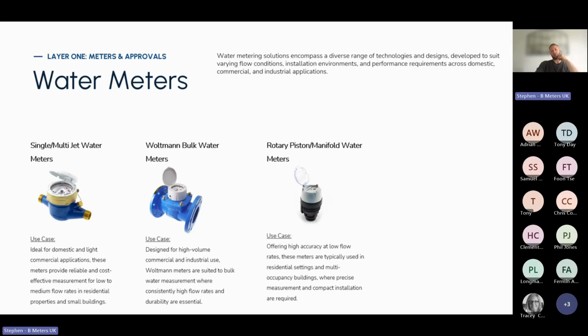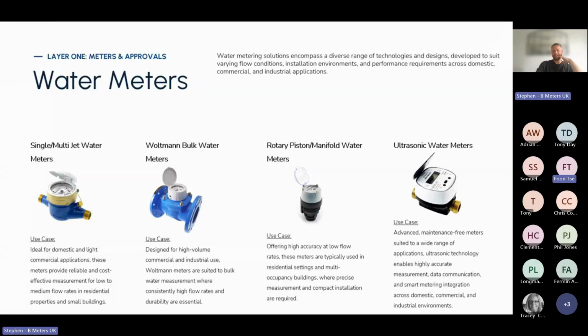Rotary piston manifold water meters are typically used in utilities and for residential use only - the design is slightly different, and you may see these predominantly with tenant valve assemblies. These are excellent at offering high accuracy at low flow rates, which is why they're predominantly used in the UK utility market, but they're also used in multi-occupancy buildings where precise measurement and compact installation are required.